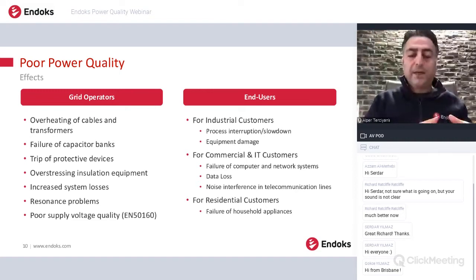Because in order to avoid the reactive power flow, you need to put reactive power compensation systems. On the other hand, these harmonics can create resonance problems on these cap banks. And of course, poor power quality results in poor supply voltage quality. There's a standard, EN 50160, which defines the quality of supply in terms of voltage magnitude, imbalance, harmonics, and also the flicker values.